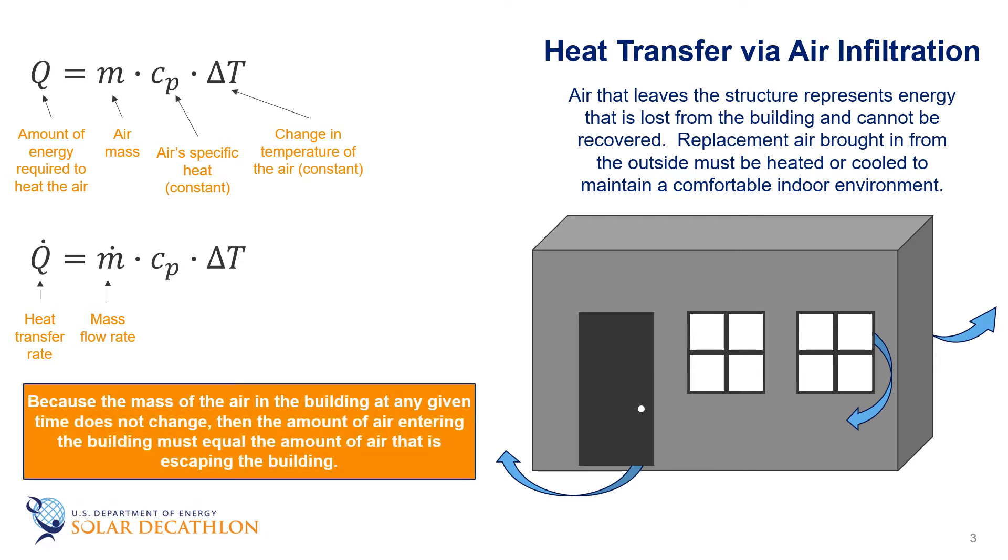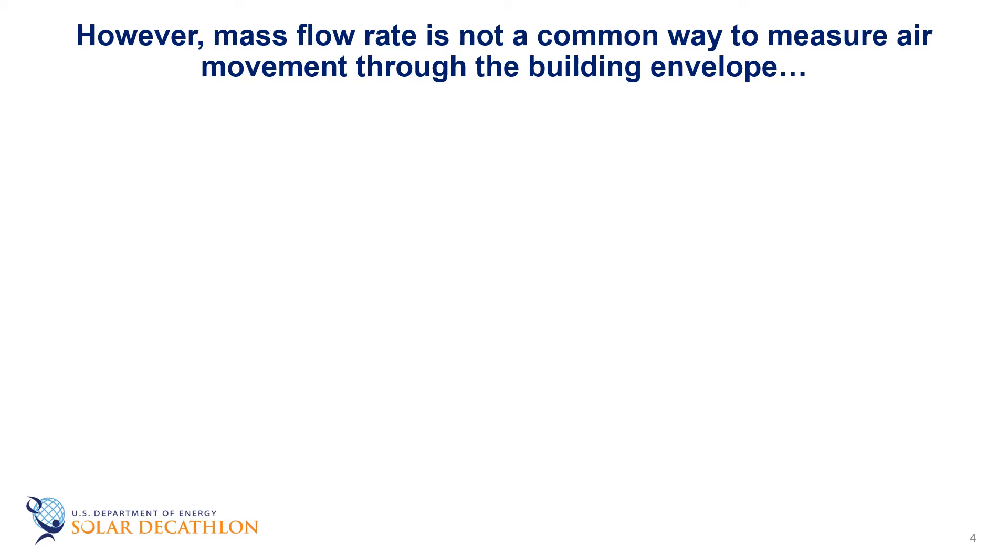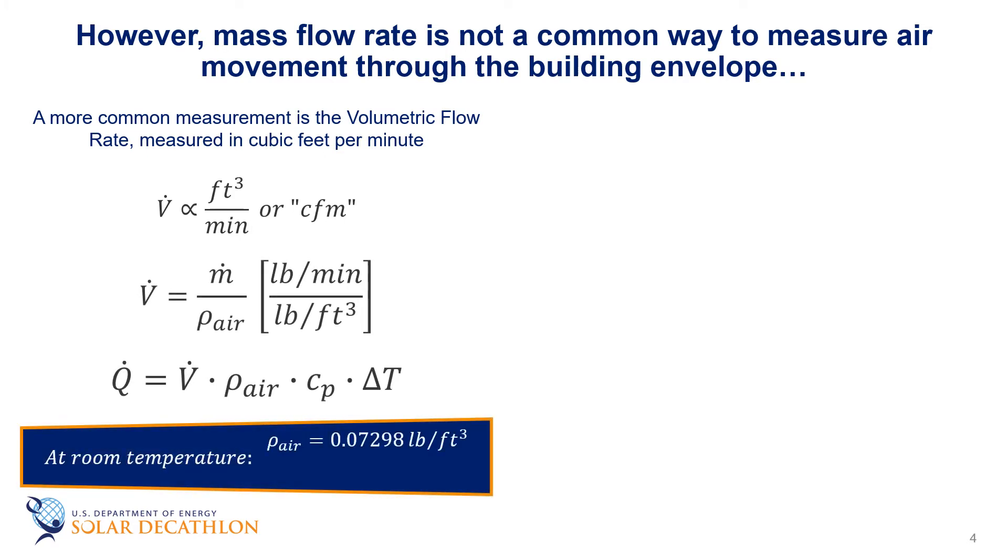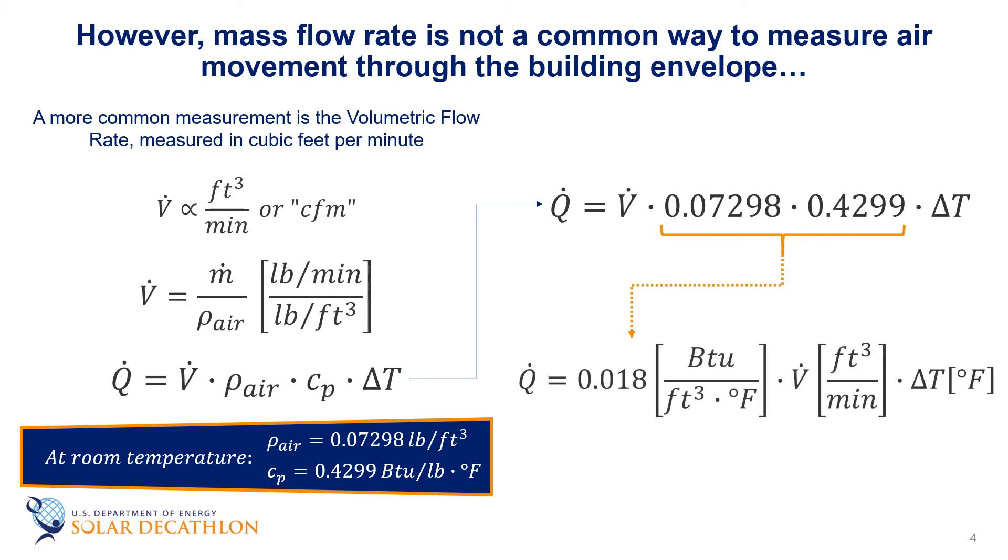Since the mass of air in the building is not changing, then the amount of air entering the building must equal the amount of air that is escaping the building. However, mass flow rate is not a common way to measure air movement. A more common way is to use volumetric flow rate, which is often measured in cubic feet per minute. The volumetric flow rate is equal to the mass flow rate divided by the density of air. Knowing that the density of air can be looked up, as well as its specific heat, we can substitute density and specific heat into the equation and end up with a simplified version, which is 0.018 times V̇, the volumetric flow rate, times ΔT, or the change in temperature from inside to outside.